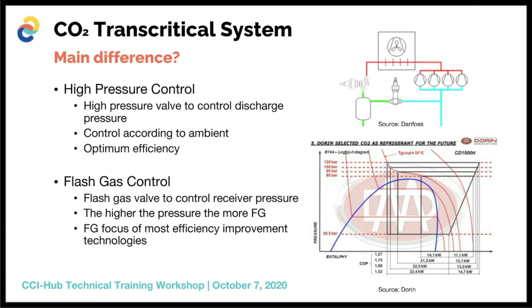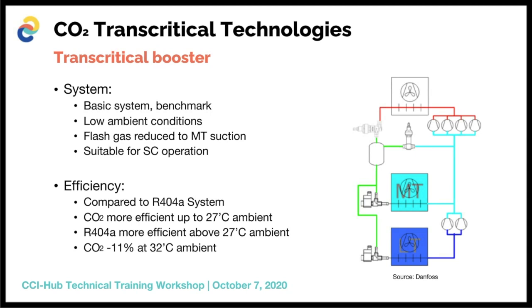Moving into available technologies, the standard system — the birth of CO2 if you want to call it that — is the basic straightforward transcritical booster system. This system has the high pressure valve and flash gas valve as additional components compared to conventional refrigerants. Everything else operates in the same way, making it a very simplistic approach to CO2 system operation.